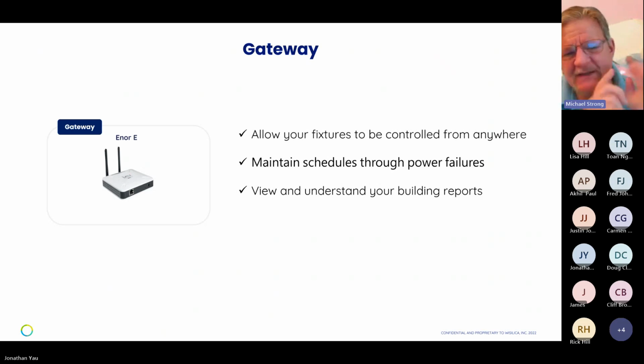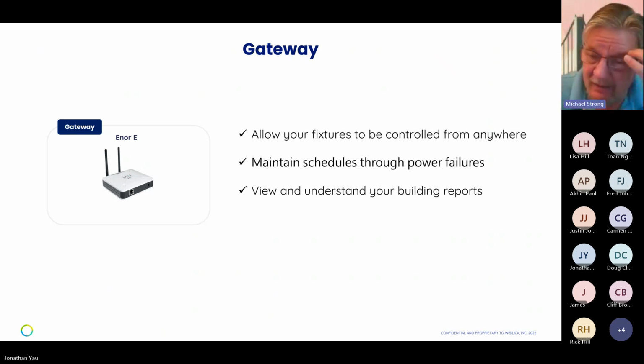So if that's the case, the eNOR-E has a battery backup built in with a real-time clock built in. It will, in a power failure, maintain the time schedule and won't forget. When power comes back on, it reminds everybody else what time it is — they know they've got a schedule, they just don't know what time it is anymore, they think it's always 12 o'clock midnight whenever they come back online. So the eNOR-E will remind them: it's really 6 a.m., not 12.